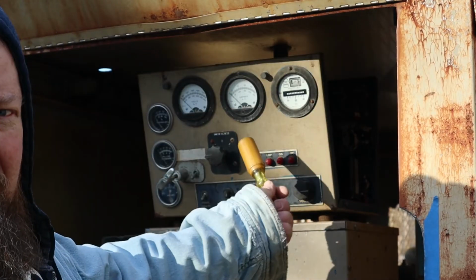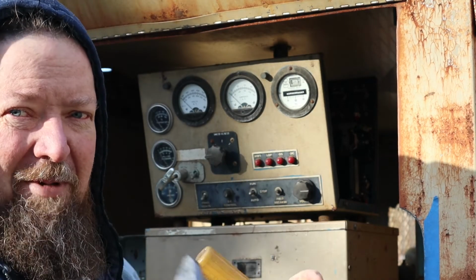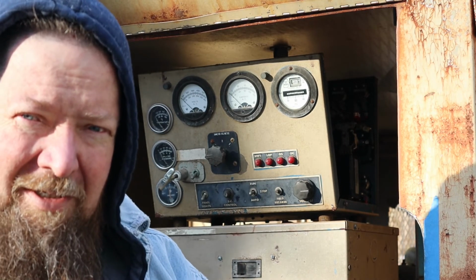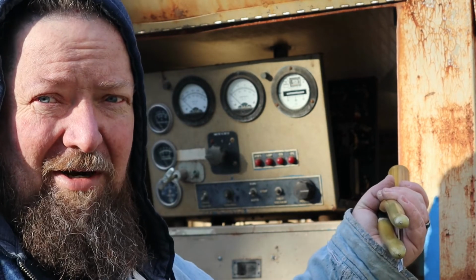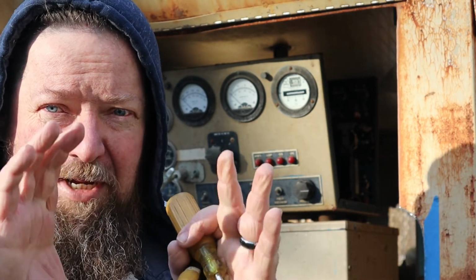We're gonna get this thing running. If this controller here don't work, we're gonna buy one of those brand new little digital ones - them things make life simple. I've wired them inside panels before, and a lot of the new generators that are out now have these little modules - everything you see, there's like 1,000 wires in that thing, but all of it can be controlled by a little dinky module. You use the same hookups, the same CTs, the same everything. I know you don't know what a CT is - that's okay, I know what a CT is. It's what reads the current going through the wire.